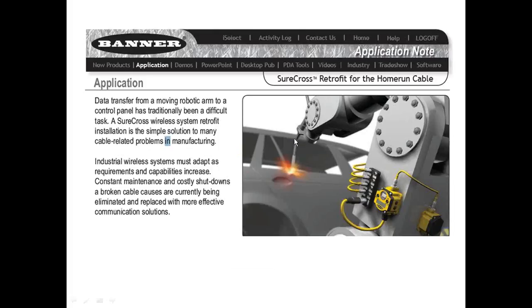Here's a robotic application, again, where you've got a battery, you've got a node here, and then you're going out and picking up I/O on the end effector. A couple of cautions here is when you're dealing with speed on the wireless, you'll see things like 65 milliseconds. My rule of thumb is that if something happens, give us a second. If you need it quicker than that, then we really need to look at the application. There are some things we can do in the sub 100 millisecond, but that gets to be a slippery slope. If you've got a second to see I/O change, then typically we don't have to worry. But that's just a rule of thumb I use.